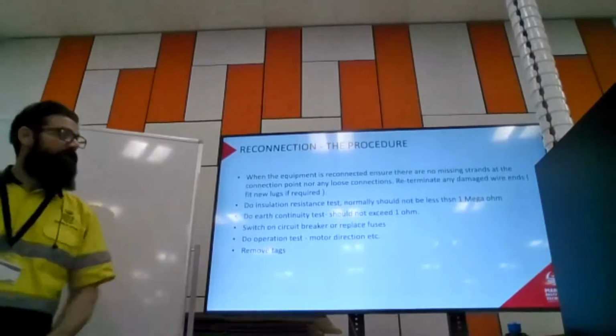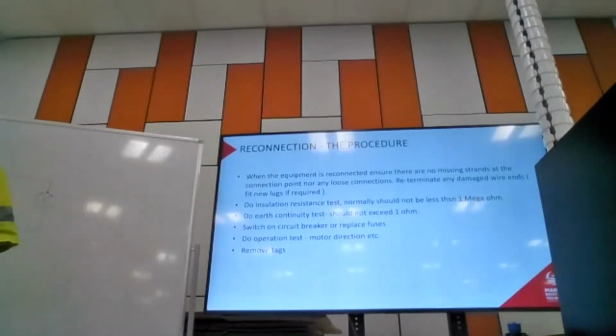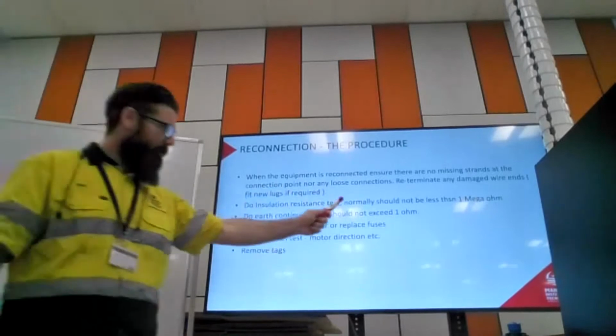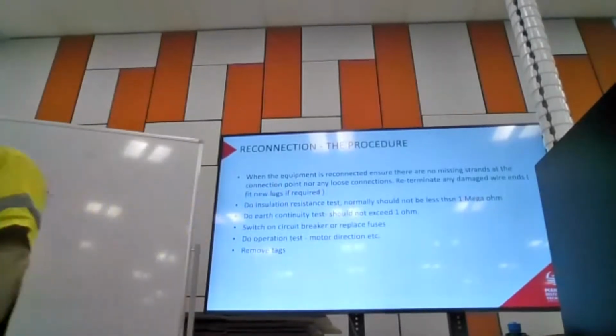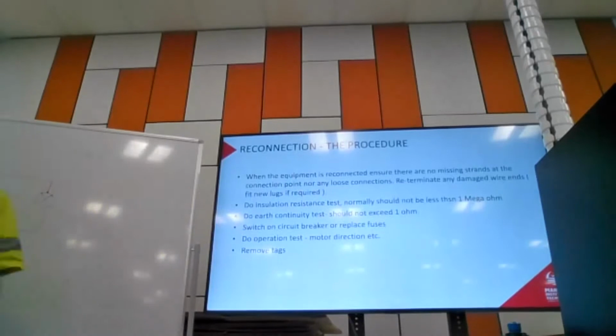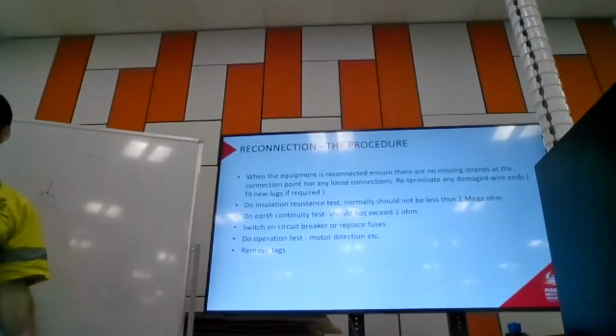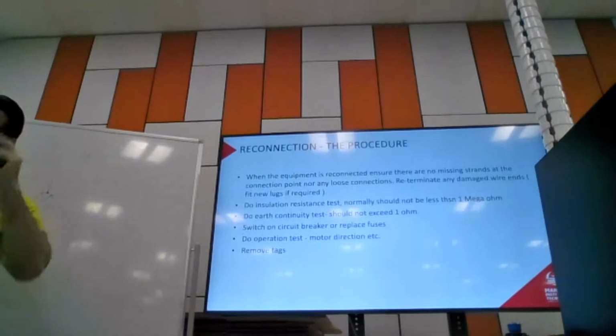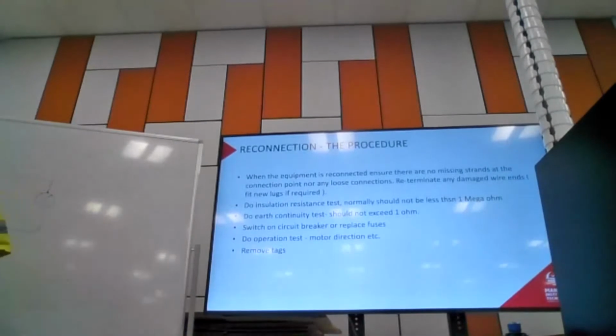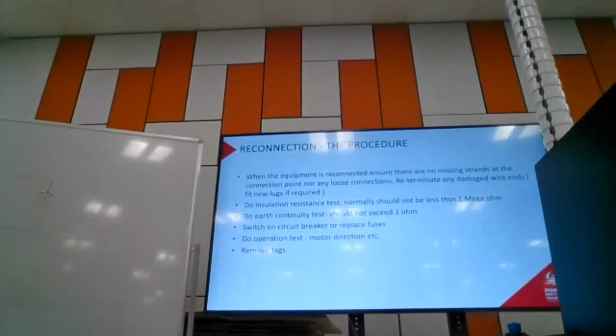We need to make sure we're doing an insulation resistance test, which normally should not be less than 1 mega. Why does it say normally? Not different kinds of wires. Any cable should have an insulation resistance over 1 mega. If it says normally, that must mean there's an exception, right? Do we remember what the exception is? Yeah, hot water cylinder, a water heating appliance. Generally a hot water cylinder, but could be an electric jug, anything that heats water.